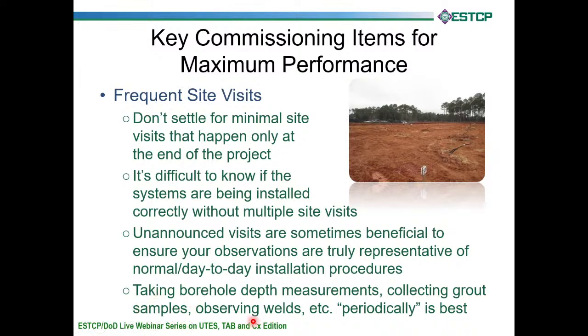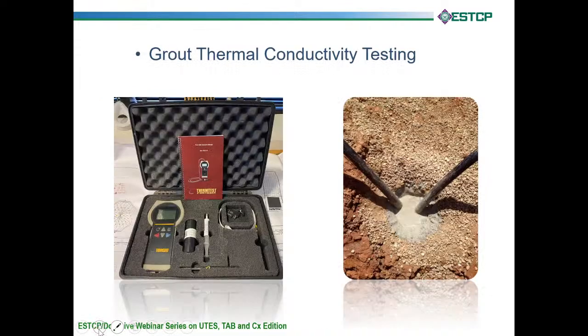When you go on site, if you're the commissioning agent, take borehole depth measurements. You can collect grout samples. You can observe the HDPE welds. And you can do that periodically throughout the construction of the GHX. Grout thermal conductivity. While you're there, you're looking at the project, take some grout samples. Ideally, multiple samples. You could even do multiple samples per borehole to make sure the batches are being correctly mixed between batches.